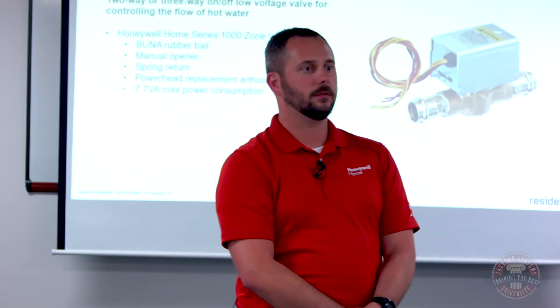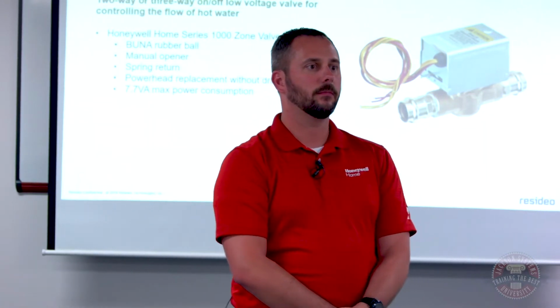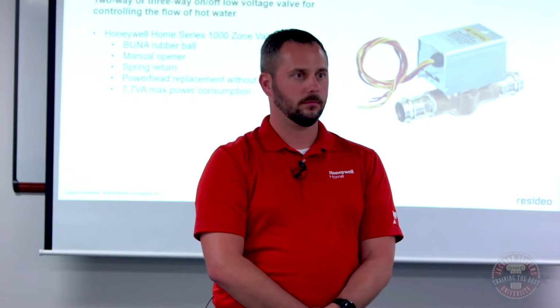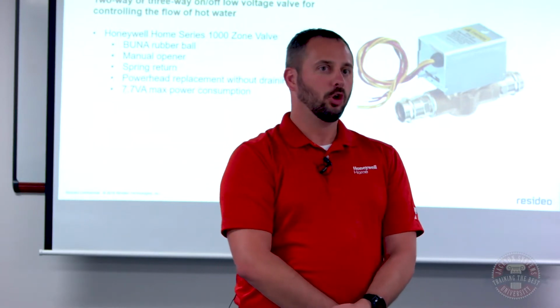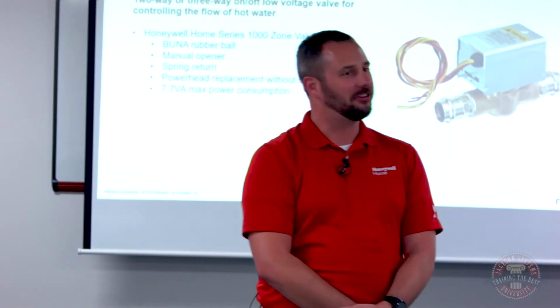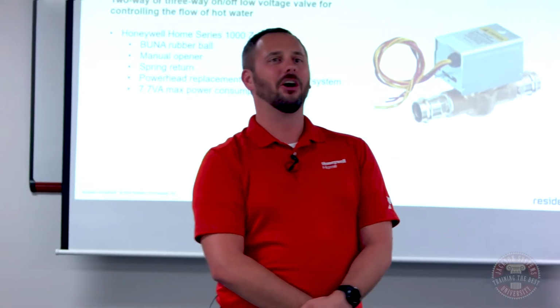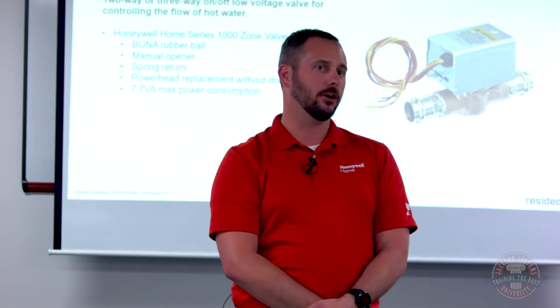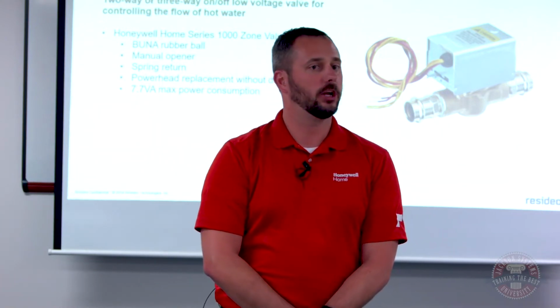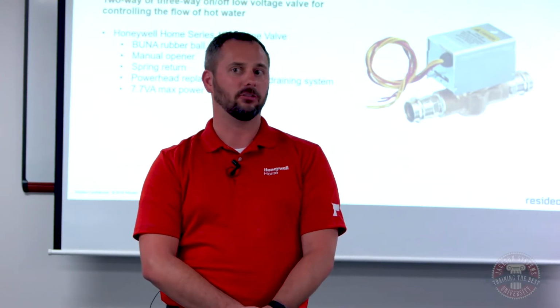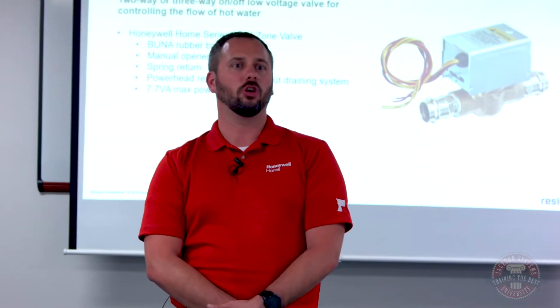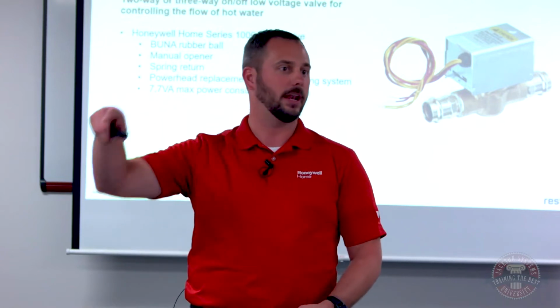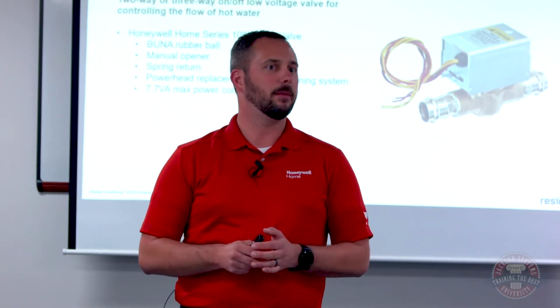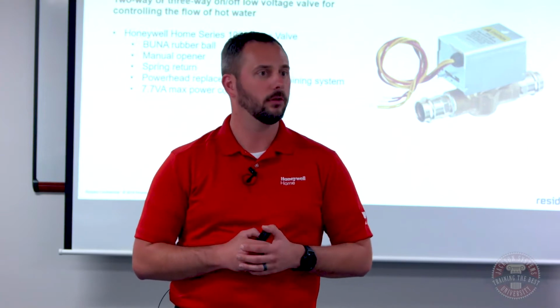Constantino asked, I thought that the Series 1000 came normally open or normally closed, depending on how you order. You said they're normally closed. Good point, and I do stand corrected. On our valves, I lean on normally closed because that's the majority of what we see. However, there are applications where you want to run normally open. I covered Canada for a little bit, and up in Canada, the most common zone valve is actually normally open, because they run such cold temperatures. If a valve fails, they want it to fail open so that the systems can still drive heat through that area. In the US, we typically see normally closed, but there are applications for both.